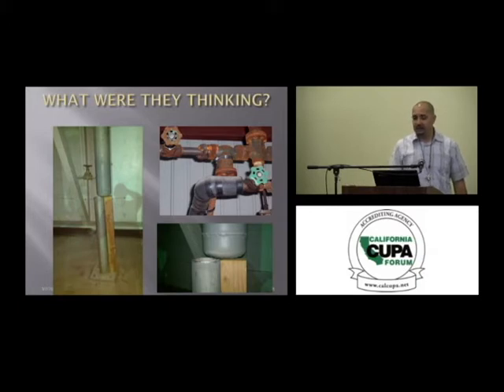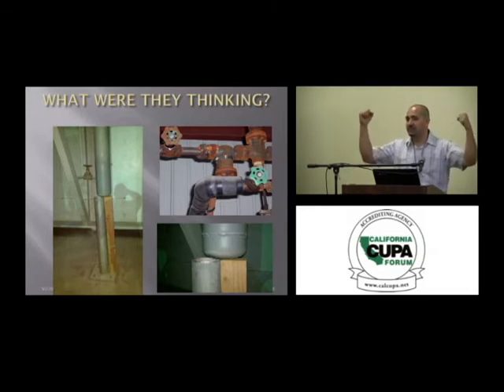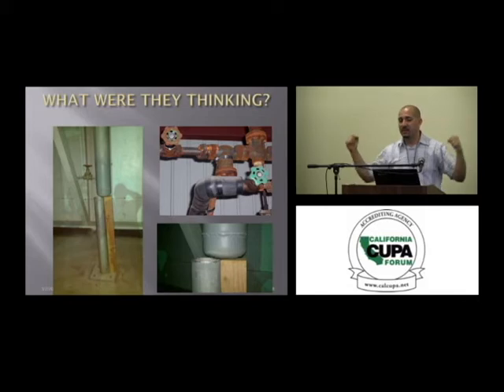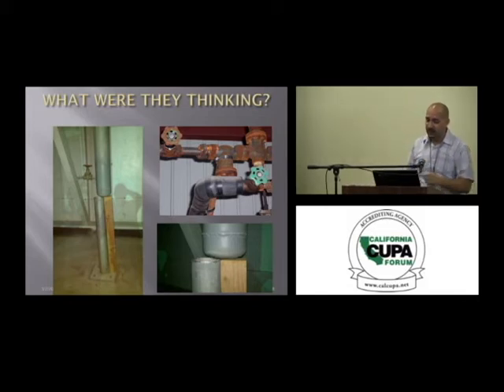Now, on the facility where this left picture is and the bottom right picture, this facility is old, not old, but just like your home, you put in a brand new home, it starts to settle, you hear the popping, the squeaking, everything kind of settling down. This facility is settling down and moving, and the dummy leg on the bottom supporting, that's a drop leg of an accumulator, it had a weld on there. And this had moved so much that it broke that weld. It takes some good pressure to break that weld.